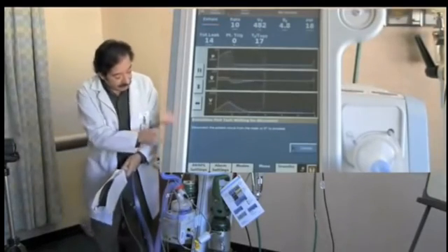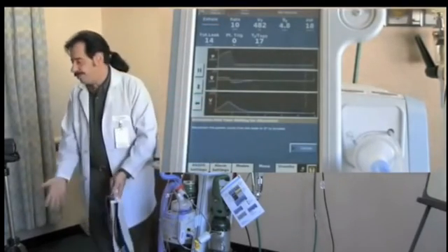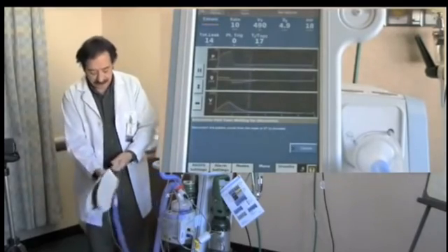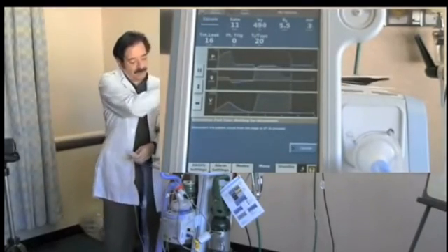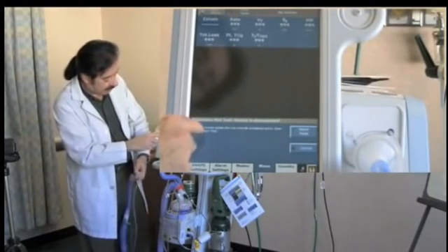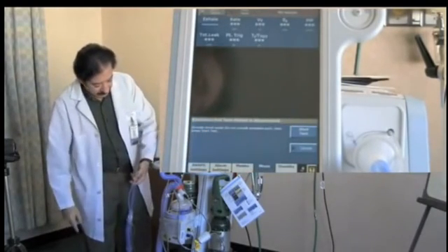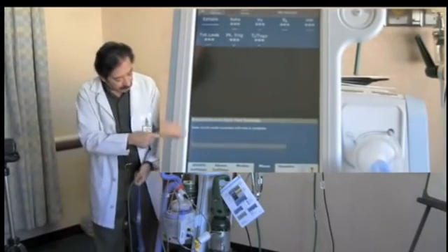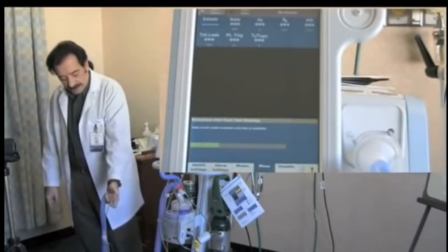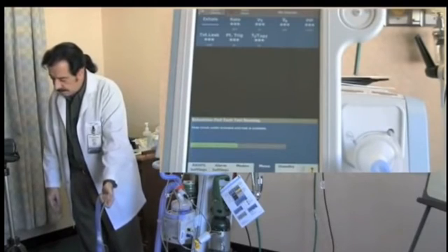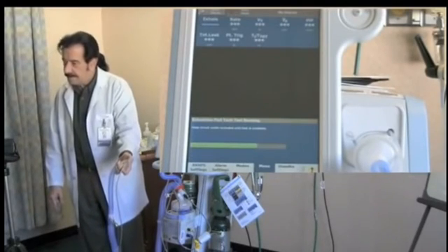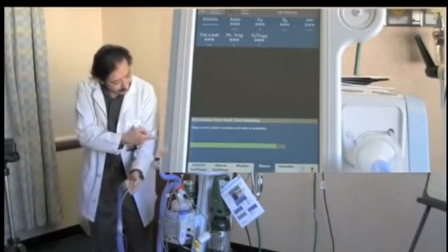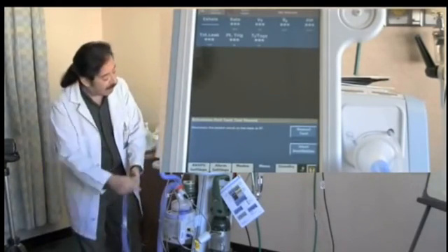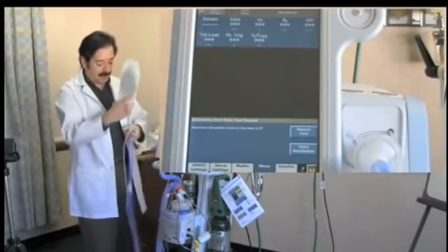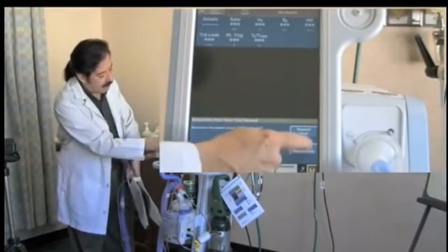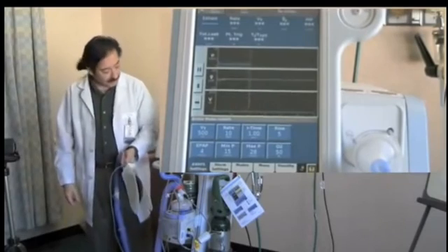So we'll disconnect the patient. It's not going to do anything until you disconnect the patient. Of course, you wouldn't have connected them yet until you've done this, okay? All right, it detects the patient's off. And now it says, okay, occlude the circuit and start the test. This bar comes up, and we'll hear it ramping up the flow. Boom. It says, okay, now I know where I'm at. So we can start ventilation. All right. And we're off to the races.